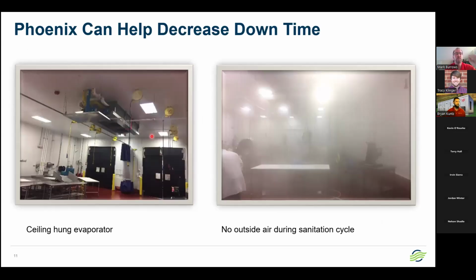Another before and after, this is another ceiling hung evaporator, which can take care of the room load during these process cycles. The issue that comes is during sanitation, right? So you don't have any way of evacuating and making up the air in these spaces. You're certainly going to have a condition like what's shown on the right. So we have makeup air, which is truly 100% outside makeup air units that operate during both production and sanitation shifts. They pair up nicely with ceiling hung evaporators to add that room pressurization piece that's missing when the ceiling hung evaporators are taking care of the room load.